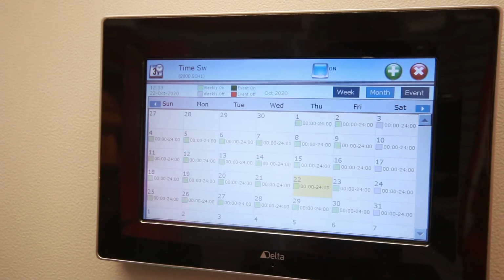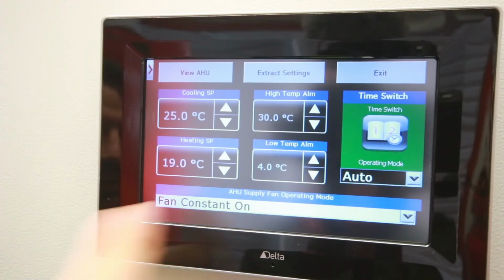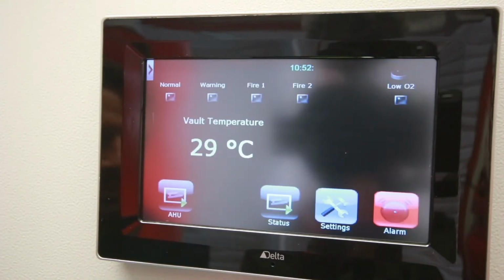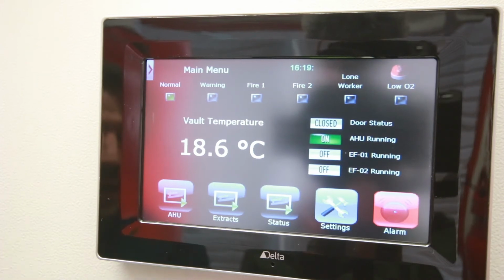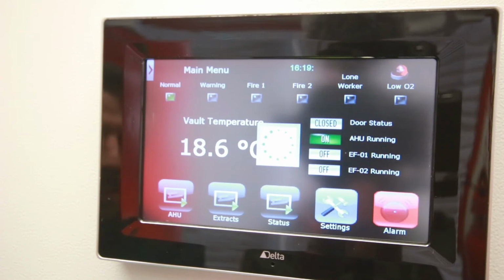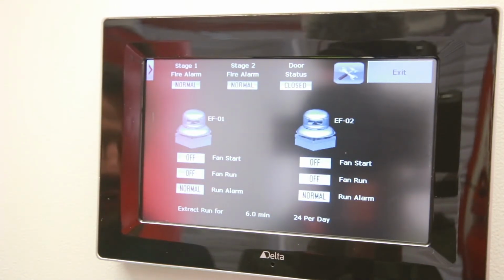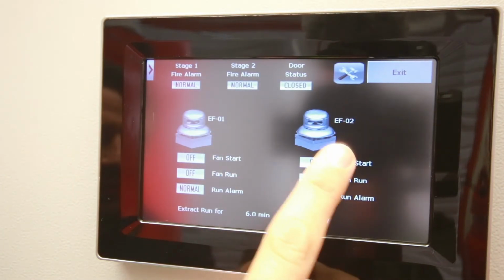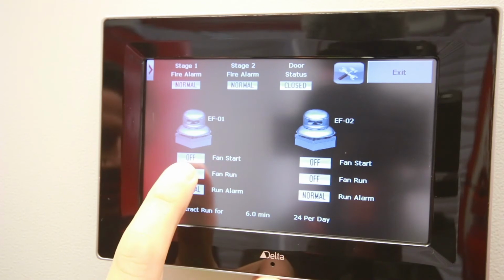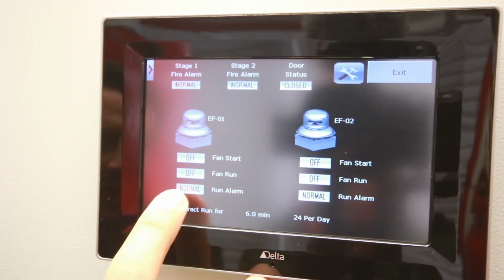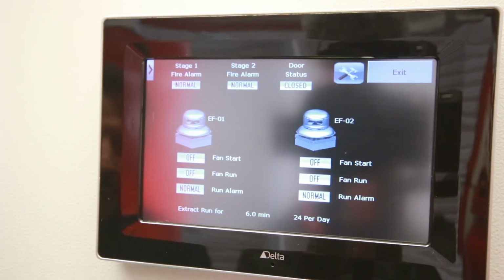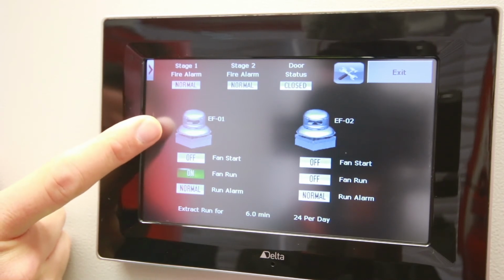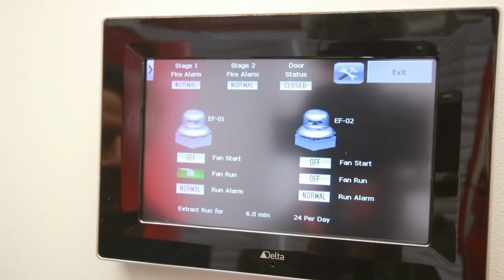You can also plan monthly events. This works in the same way. To return to the home screen, simply hit Exit. Now we can look at the Extract menu. With this system here, we've got two extract fans, EF1 and EF2. Here we can see the fan start alarm is off, the fan run alarm is off, and everything is running normal. If we were to turn the extract fan on, the graphic changes to indicate a rotating fan, and our fan run power lamp is active.